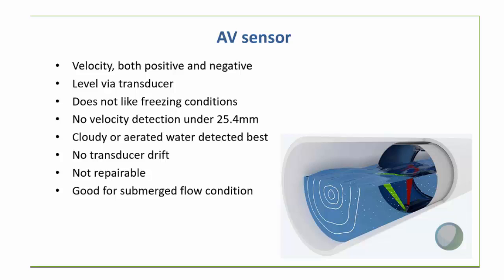The area velocity sensor will measure in both the positive and negative directions. It does have a level transducer as recorded by a pressure transducer, which, as you can imagine, does not like freezing conditions. And similar to what we just heard from Shinhua, we do have a minimum depth of 1 inch, or otherwise no velocity is recorded. Our experience is it generally works better under cloudy or aerated water, but we have started to see, and been working with ISCO to make it more sensitive. We have some pretty clean water in cases, and we are still seeing some pretty good results.